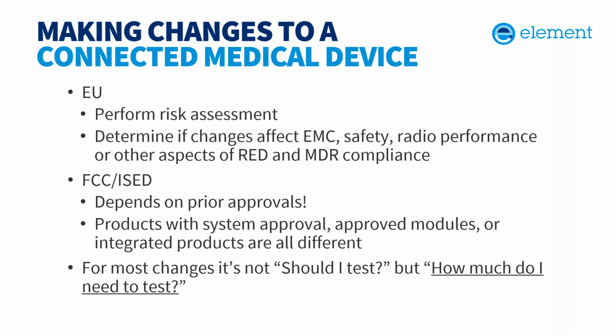Another example is if you want to change the antenna or add an antenna. Typically, that's going to require at least some testing. If you're changing vendors on a part, let's say it's a non-radio part, so you've got your radio, you're not changing that at all, but in your medical device you need to change a part out. Well, it probably won't require certification, but you still need to do testing to verify that you're still meeting those legal requirements of the FCC. Another example is if you're depopulating, if you've got a product and you're going to pull part of it out to make a budget version. You can do that, but testing is still required. Usually it's a good idea to test both the fully populated and the depopulated version during the initial certification work because it streamlines things and is going to save you money. You're going to want to reach out to your local test lab for specific guidance, because changes can be very complicated.